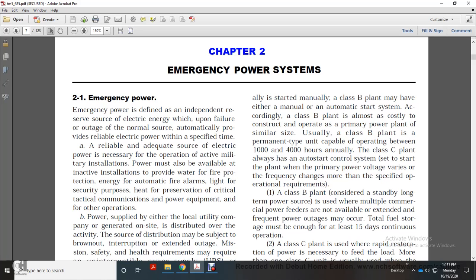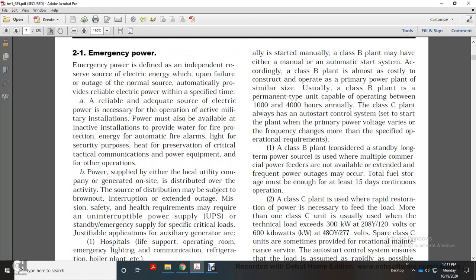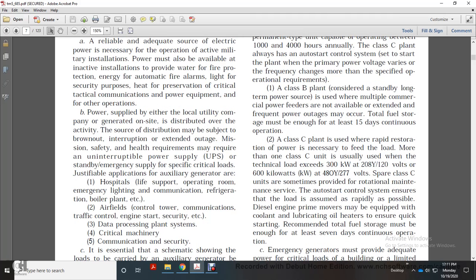A Class B plant is generally considered a standby long-term power source used when multiple commercial power feeders are unavailable and frequent power outages occur. Total fuel storage must be enough for at least 15 days of continuous operation. Class C plants are used for the rapid restoration of power. When technical loads exceed 300 kilowatts at 208Y/120 volts or 600 kilowatts at 480/277 volts, more than one Class C unit is typically required. Total fuel storage for Class C must be enough for at least seven days of continuous operation.